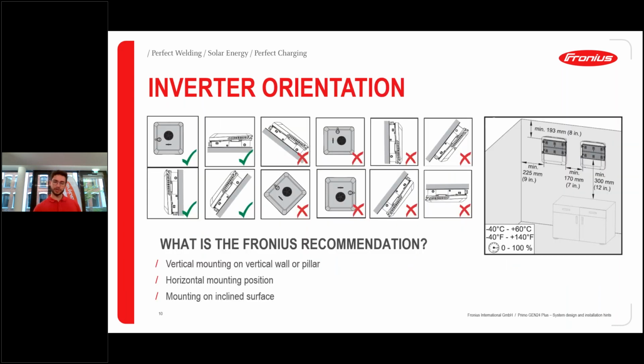Regarding the orientation or the positioning, we can install it vertically and also up until a horizontal way without any problem. Also in a slightly tilted angle, this is no issue. The only thing we need to make sure is that it's not tilted sideways, so that the cable gland is not doing its job anymore. If you tilt it sideways, you could possibly have water through the cable glands into the device, and this is of course a big issue. So as long as you don't tilt it sideways, it's no problem.